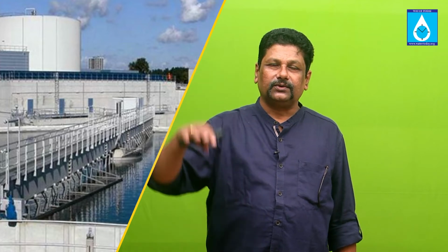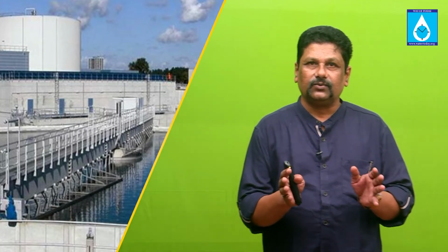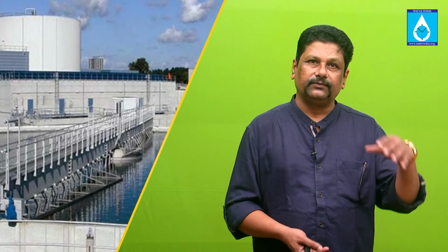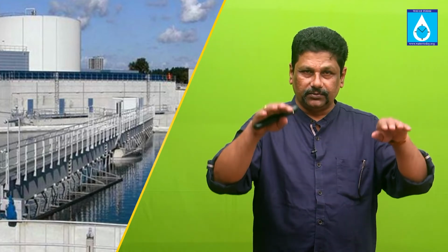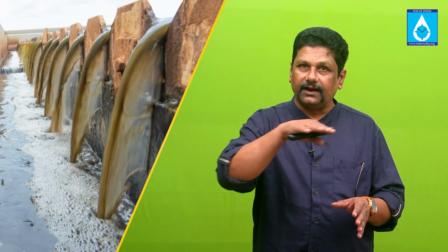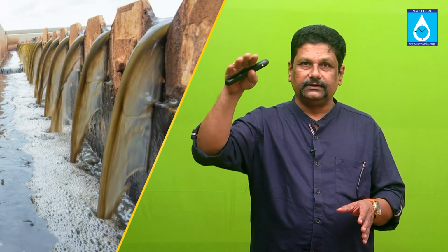So what should be the start and stop? See, it all depends on what kind of pump you are getting. Today pumps are available with cooling jackets, which means that even if you pump it low, just above the volute, you can still pump it if you have a cooling jacket. But if you don't have a cooling jacket, it is always advisable to completely submerge the pump and have your low level just above the complete height of the pump. So the start level, the stop level, you can also have an alarm level, and this is how sewage pumping operates, and you should be very careful about having the right levels inside the pumping pit.